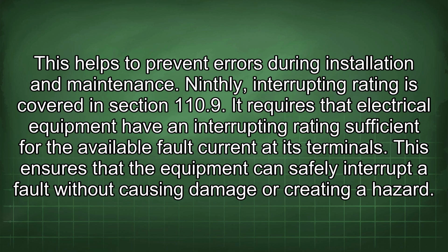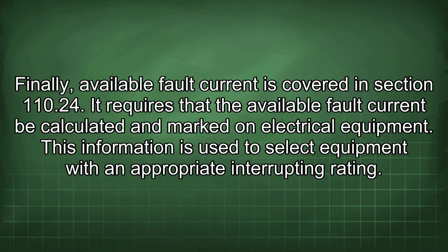This ensures that the equipment can safely interrupt a fault without causing damage or creating a hazard. Finally, available fault current is covered in Section 110.24. It requires that the available fault current be calculated and marked on electrical equipment. This information is used to select equipment with an appropriate interrupting rating.